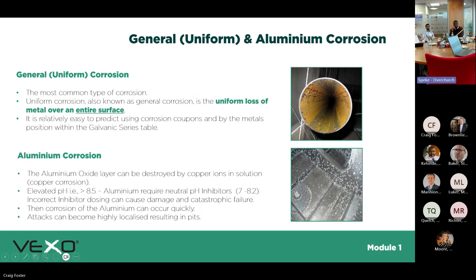General and uniform corrosion is across the whole pipework — typically when there's no inhibitor, and the water constantly reacts with the entire surface area. Pitting corrosion looks more like pinhole attacks, caused by galvanic corrosion, where certain areas without inhibitor solution become anodic and the water attacks those small specific points.